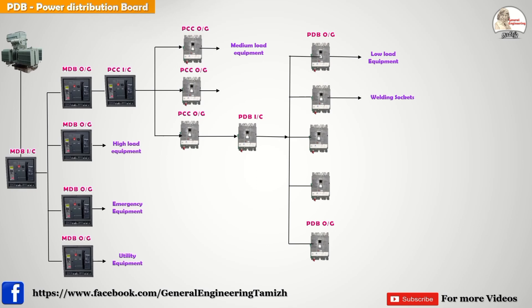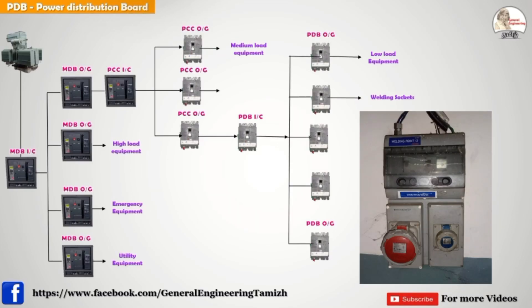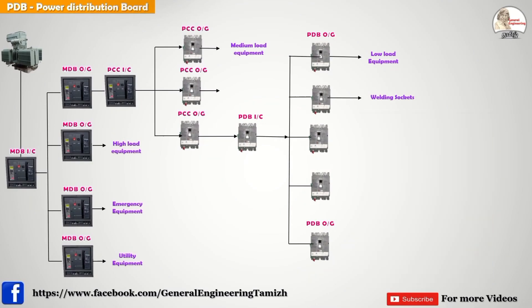Next, there is a welding circuit. Across the plant you can see this type of circuit — it's for portable tool connections like grinding machines, welding machines, and cleaning machines. That supply is connected from the PDB. Also, three-phase AC systems — such as split ACs and packaged ACs used in industry — are supplied from the PDB. Additionally, three-phase ventilation systems like large exhaust fans, air handling units, and air coolers are also supplied from the PDB.